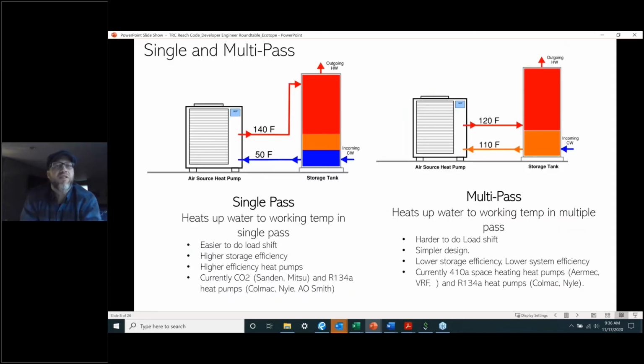So, moving on to the 2 different ways to do heat pump water heating at a central level. There's the single pass operation. Single pass is really heating your water up to the working temp in a single pass. Pretty straightforward. Typically, you're pulling from the bottom of a tank and you're dumping to the top of the tank. This is a really effective way to do load shift, and this is really what the region is focused on. With single pass devices, especially CO2, we can make really hot water in a single pass, and that really helps to facilitate load shift.